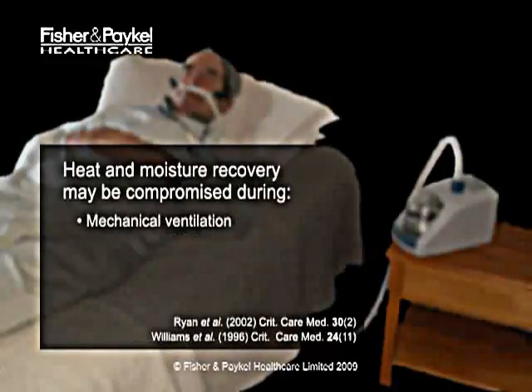During mechanical ventilation with room air, or bypass of the upper airway by tracheostomy, cool, dry, unconditioned air desiccates the airway mucus. Again, mucociliary clearance breaks down through the dehydration of the mucus. Viscous mucus accumulates in the airways. Coughing, a backup mechanism for clearing mucus, increases to try to clear the buildup. Inspired air, heated to body temperature and fully humidified, restores the physiological equilibrium, increasing mucociliary transport and reducing the need to cough.